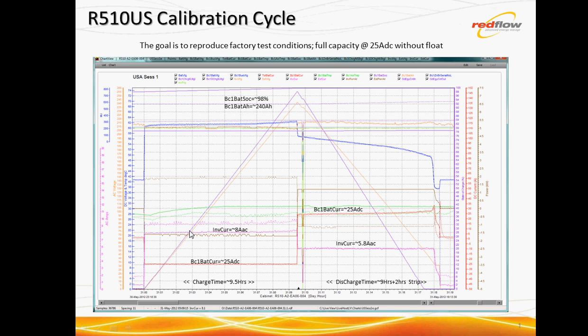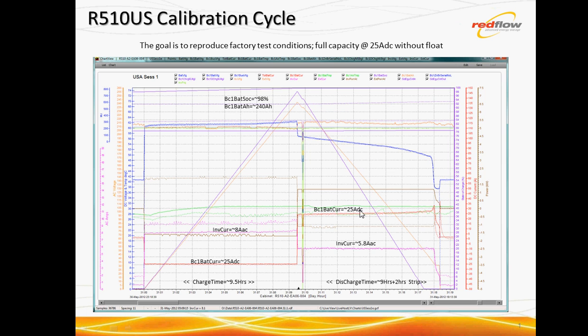And with that, we see the state of charge getting up to slightly under 100% and 240 amp hours, which is the sort of scale we're looking for. And then on the discharge, slightly lower inverter current, 5.8 amps AC, which will give you on average 25 amps DC over the cycle. And that's going to take about nine hours to occur. You need to allow another couple of hours for the strip to happen.